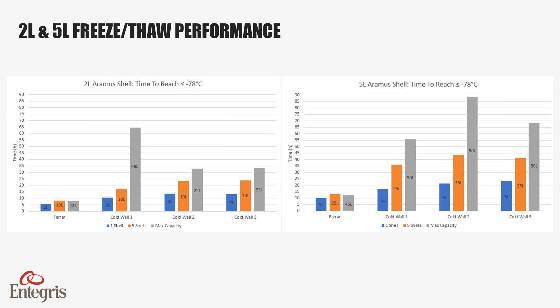What you'll note here is that there is a very large difference in the freeze time for each of these different freezer types. For our freezer on the left-hand side, there are significantly faster freeze rates, as well as being much more consistent between the different fill volumes inside of that freezer. So overall, a much higher freeze rate to match that footprint data that Scott showed us earlier in the presentation. Overall, much faster freeze rates are achieved in the FARRAR controlled rate chamber than any of the cold wall freezer options tested.